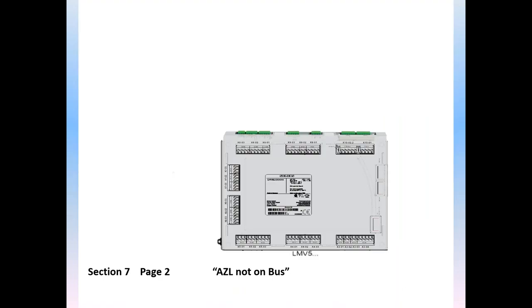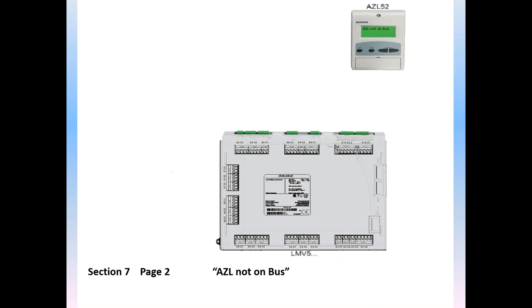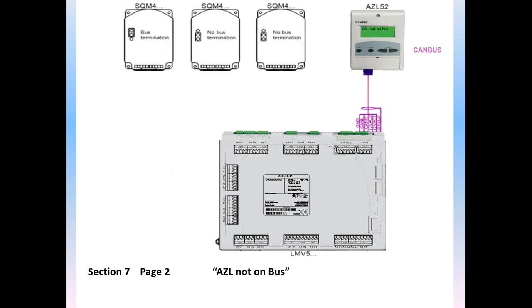Let's take another common fault: AZL not on bus. This is probably the strongest fault you can get on the LMV5 system. What it's telling you is that the CAN bus network is no longer communicating — it can't tell you what the fault is because there's no communication going on whatsoever. The LMV5 basic unit needs an AZL display for the human interface, connected by means of a CAN bus connection. To run the burner, we also need actuators for air, gas, and fuel — and those must also be daisy-chain connected by CAN bus connections. This is the CAN bus communication network, shown in purple, between the servos, the LMV, and the AZL display unit.